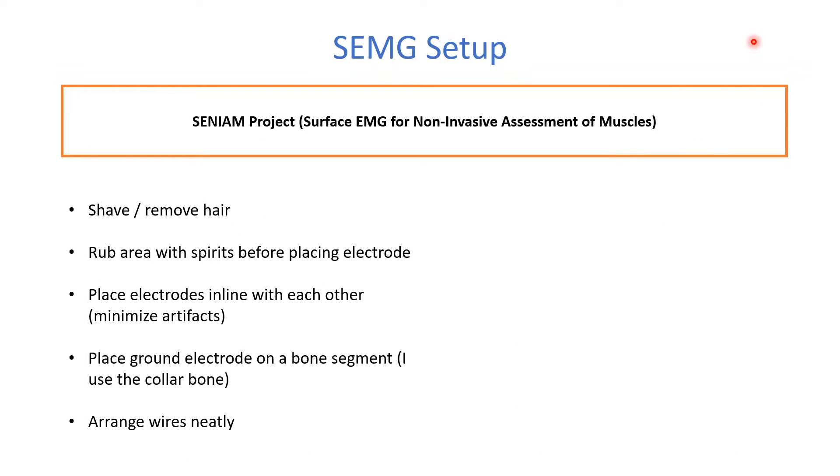The effectiveness of SEMG greatly depends on how well you place the electrodes and set the system up. Now, if you want the exact details of what procedures to follow and at what locations the electrodes should be placed for each muscle, you should check the Seniam project, its website online which is more or less the standardization body for SEMG. Apart from this, a few points to follow would be to shave or remove hair in the area where the electrode will be placed, clean it with spirits and keep the electrodes in line with each other and make sure the wires are arranged neatly to avoid people tripping or tearing the wire. Care should also be given when placing the ground or the reference electrode. You should place it on a bone segment. I typically use the collar bone for this purpose.